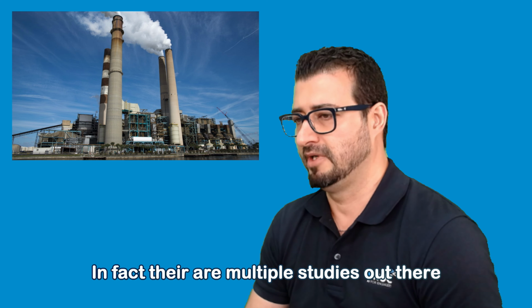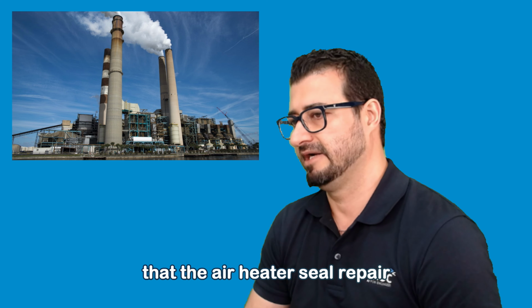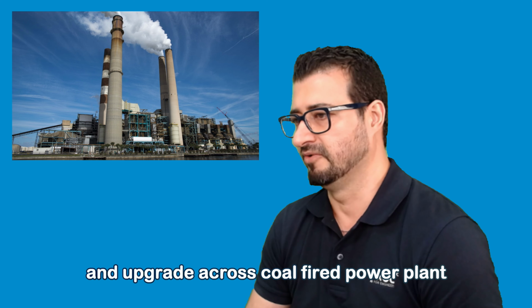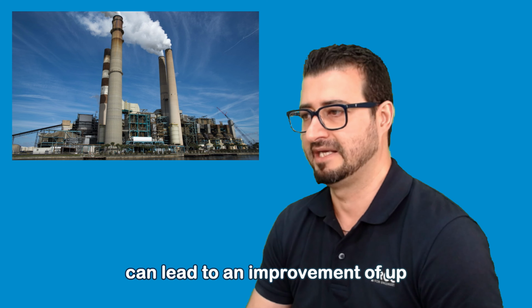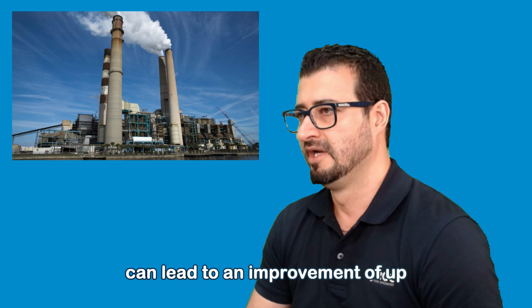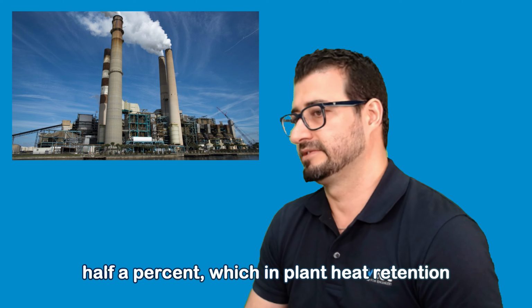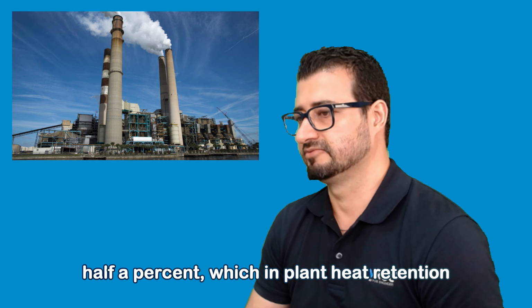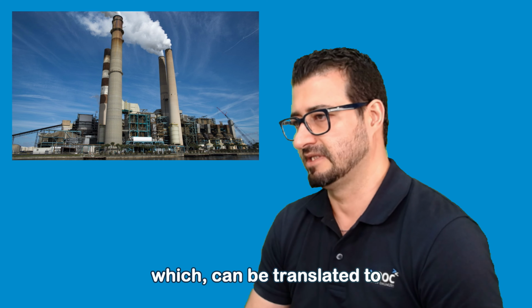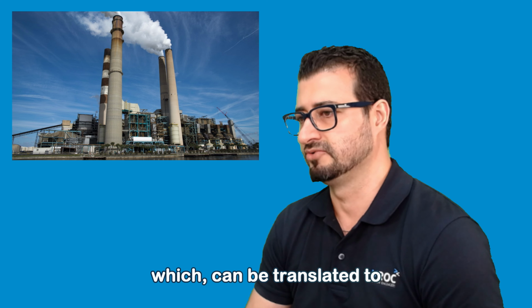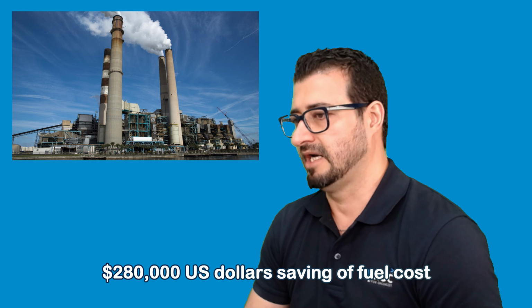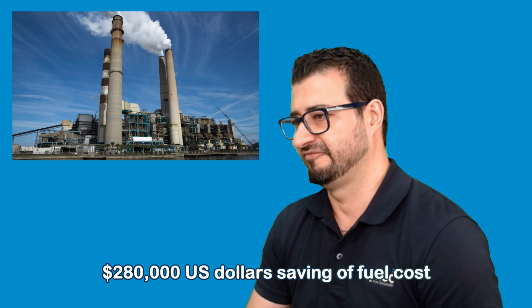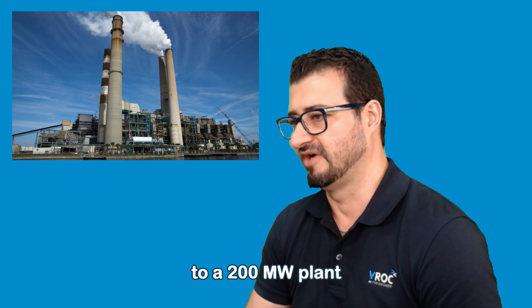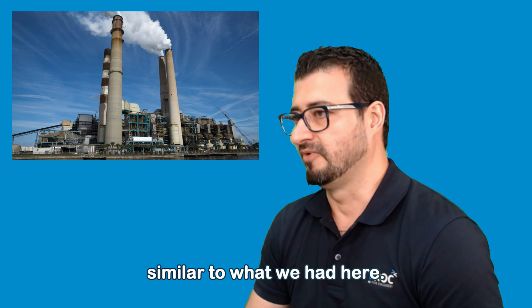In fact, there are multiple studies out there showing that air heater seal repair and upgrade across coal-fired power plants can lead to an improvement of up to 0.5% in plant heat retention, which can be translated to $280,000 saving of fuel costs for a 200 megawatt plant, similar to what we had here.